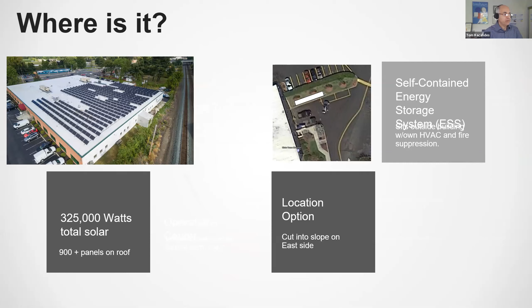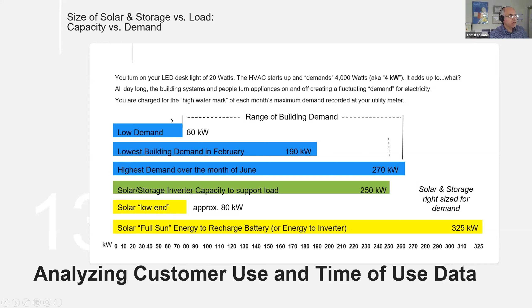This particular customer, on a Sunday when not a lot of employees were there, had 80,000 watts of demand at any given moment. But in the middle of summer, with AC cranking and lots of people sweating, they'd hit 270,000 watts. That's what kW is. And if we have an inverter supplying that AC with a capacity of 250 kW, this relationship of peak and low demand to inverter capacity is a feature of us supporting load.